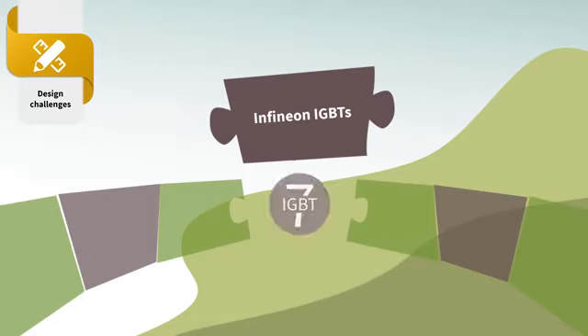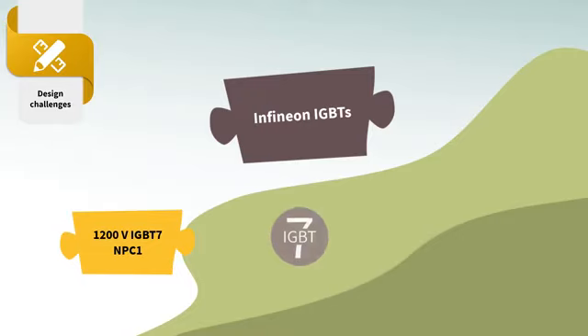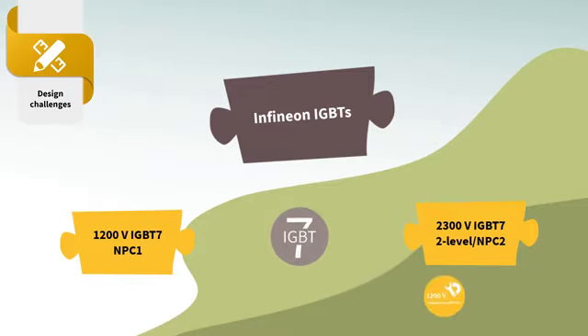Infineon developed two IGBT technologies to meet the market needs. The 1200 volt IGBT-7 in dual configuration to build the NPC1 topology, which aimed to decrease the system costs and allow a performance optimization with minimal design changes, keeping the state-of-the-art power level of 1.1 MVA. And the 2300 volt IGBT-7 in a simple two-level topology or an NPC2 topology, in combination with a 1200 volt common collector configuration, which aimed to address the next level of power and performance but with a change in the inverter's topology.